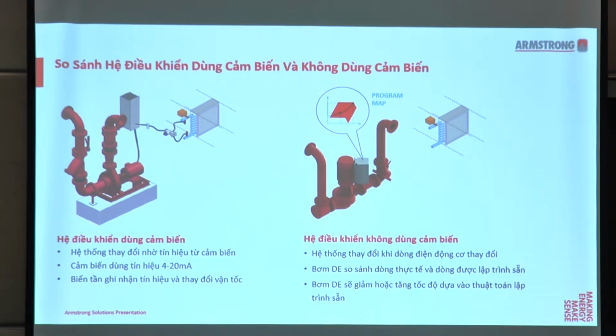drive with all our embedded information. Again, the 4 parameters that we embed into our drive will be power and speed, flow and head. Okay, so a change in the system is read by a change in the power drawn of the motor. Okay, and what happens is that our pump will actually compare the power drawn against the data that is already included in the pump, and that is where you will read what is the head and flow that it's operating at. Okay, and of course it will have the speed modulating function based on the readings as well.